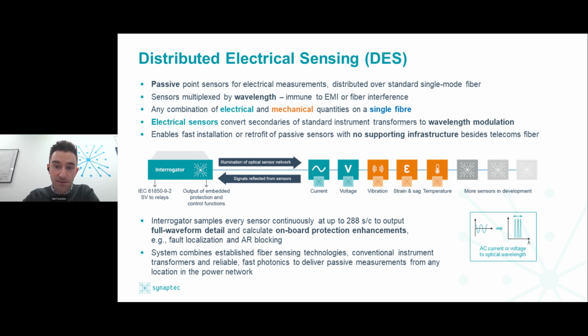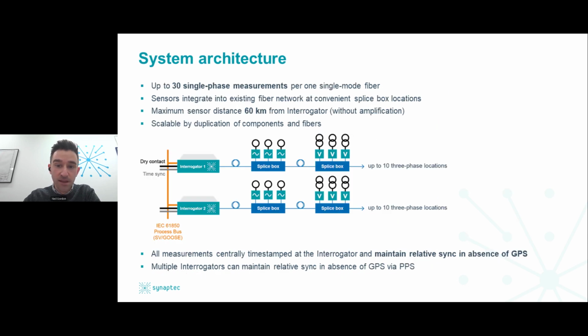So this method combines established fiber technologies with trusted standard instrument transformers like current and voltage transformers, allowing current and voltage measurements to be deployed over long distances outside the substation fence and with no supporting infrastructure besides that telecoms fiber. So in terms of the system architecture, each single interrogator can support up to 30 single-phase measurements or up to 10 three-phase locations on one single-mode fiber.